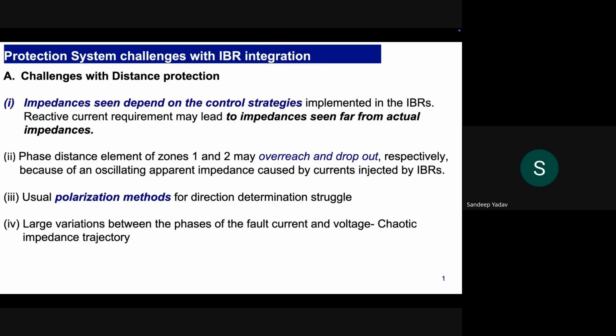Challenges with distance protection, we talked about it. The impedance which is seen by the relays depends upon the control strategies of the OEM. So the current injection with respect to voltage may vary with the control strategy, and that is why the impedance which is seen into the system by the distance relays also varies considerably, right?